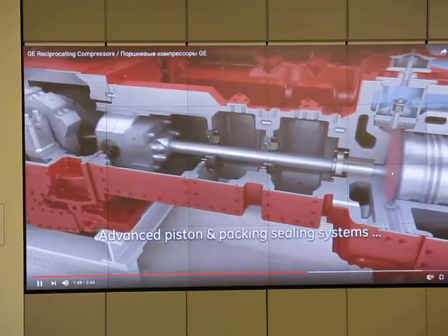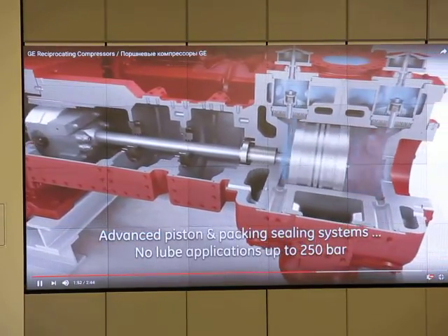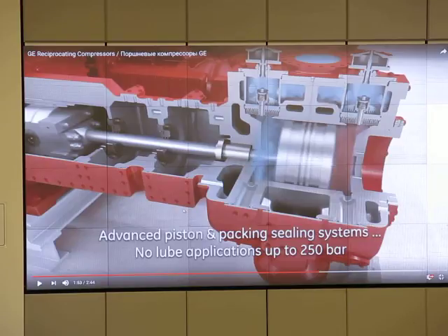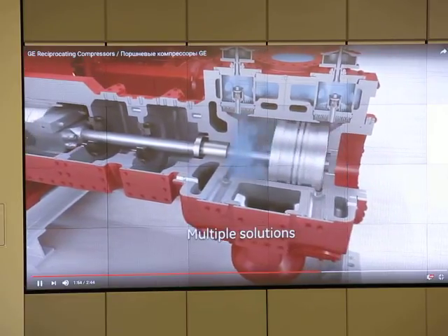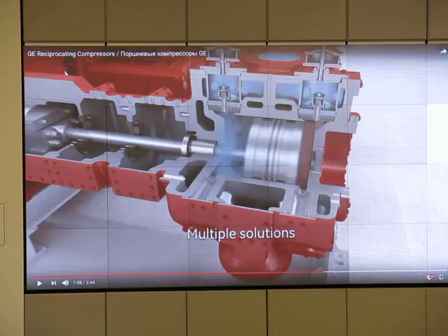So you compress either way, right? Red means higher pressure, blue means lower pressure. So when you push forward, the chamber on the right-hand side becomes red, so you compress that side. When you pull backward, the other chamber becomes red. So for one revolution, you compress either way. So this kind of thing is double acting, not single acting. Single acting means we compress only when we push. Here, whether we push or pull, we compress both times. So this kind of compressor is double acting, and you have valves on both sides.